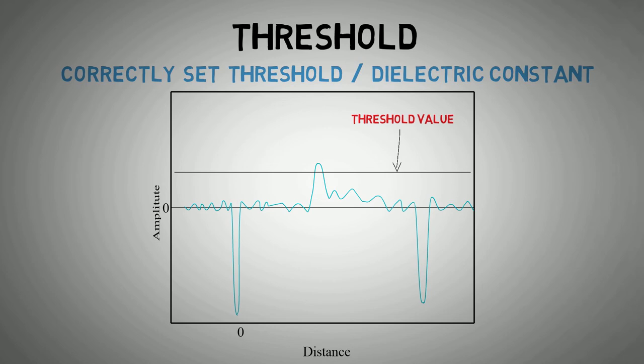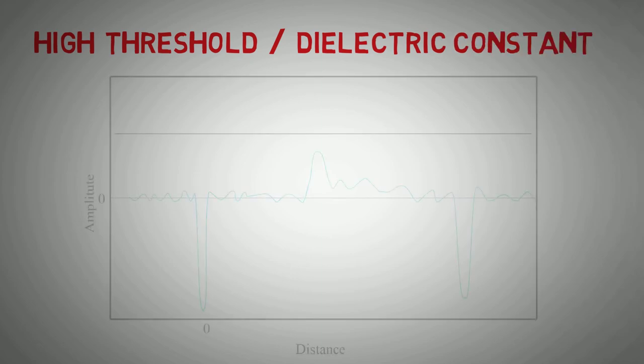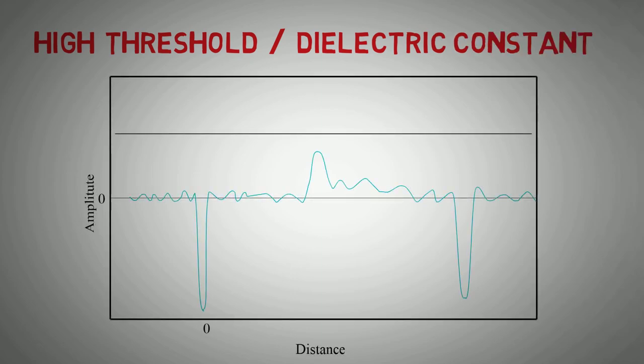If the dielectric constant is set up incorrectly, the level amplitude threshold will also be incorrect. Depending on the values selected, an incorrect dielectric constant could cause a number of issues. In the first instance, the threshold will be set too high. Looking at a threshold that is set too high, this causes the surface reflection to be ignored, meaning the transmitter will read zero.